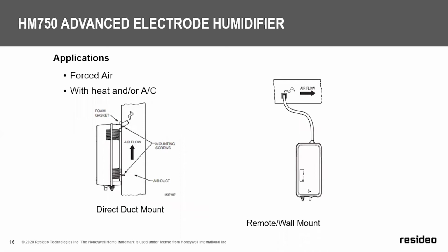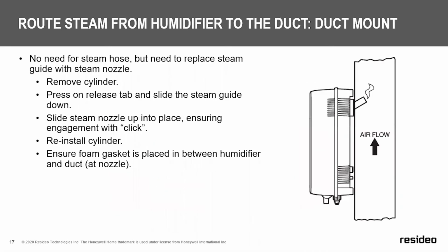Here we show the two diagrams for installing. On the left, we have the direct mount. On the right, the remote wall mount, or remote duct mount in some cases. When direct mounting it on the ductwork, there's no need for the steam hose, even though it's included in the box. You will remove the cylinder and slide out the steam guide and install the nozzle for direct steam input. It'll click when it's fully seated, and then you will reinstall the cylinder, making sure that the foam gasket is placed in between the humidifier and the duct nozzle.